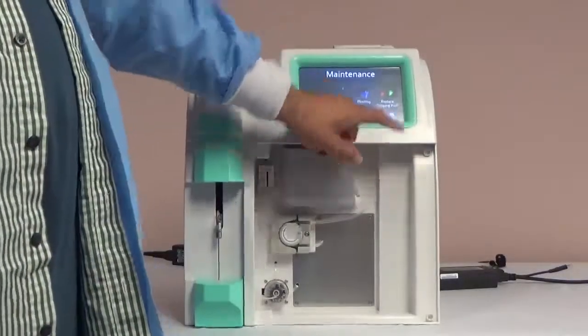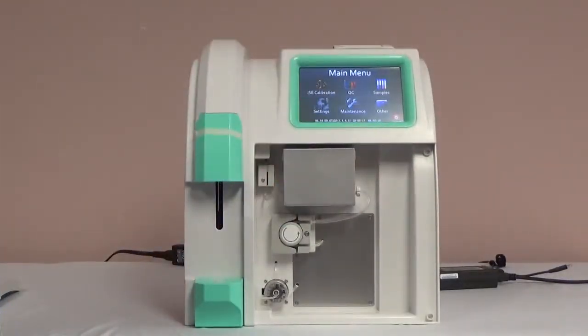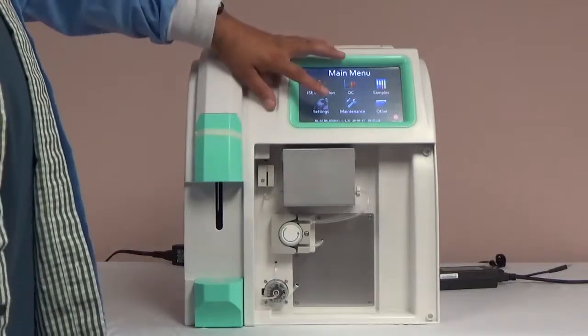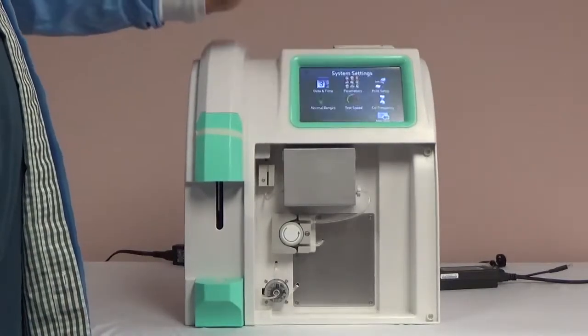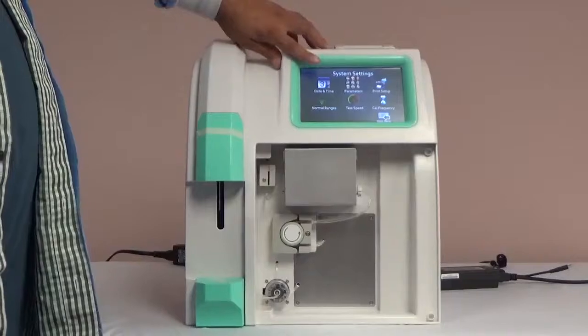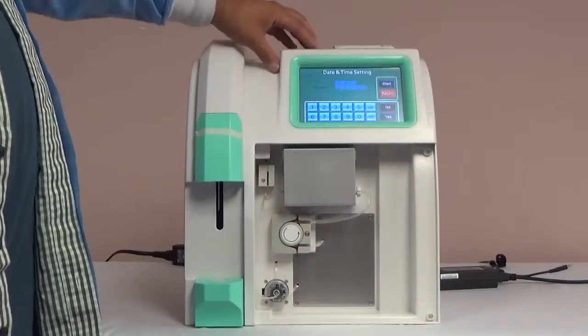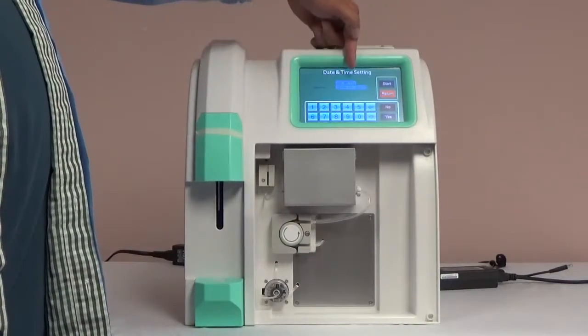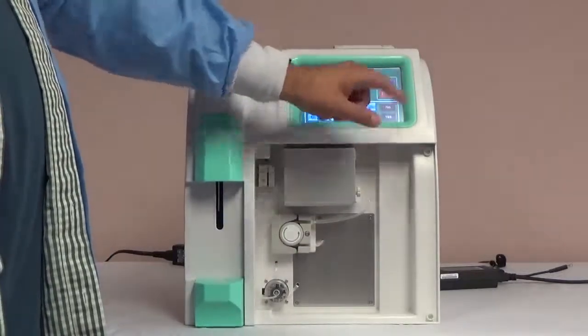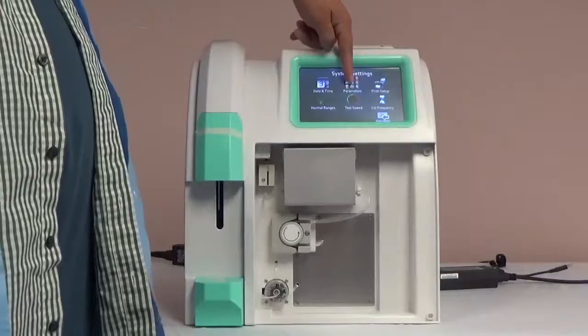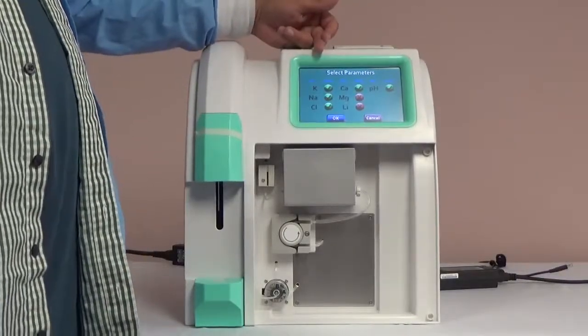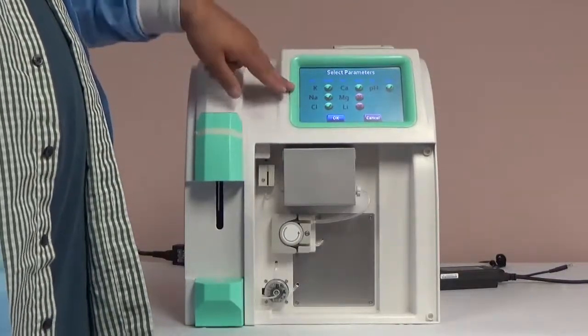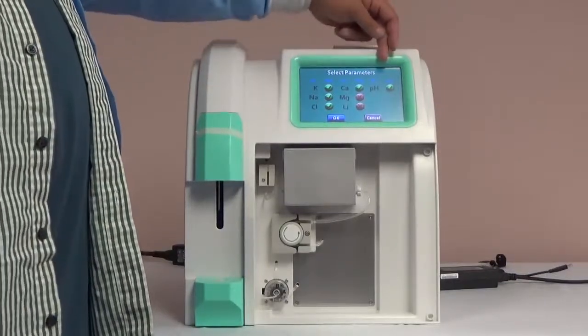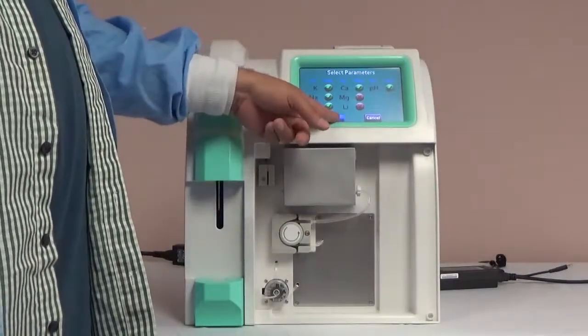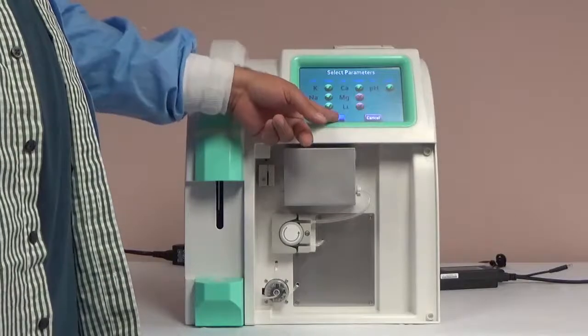After the pack is primed, go back to the main menu to begin adjusting the main settings, starting with the date and time. Click Settings, then Date and Time, press Start, and enter the correct date, then time, press Yes, then Return. Back on the System Settings screen, the Parameters option will show the selected parameters for the model analyzer you are using. You can use this menu to select the parameters you wish to test. All available electrodes are selected by default.